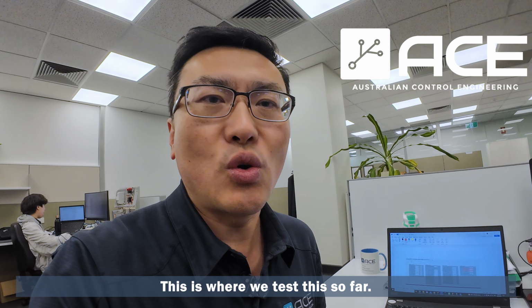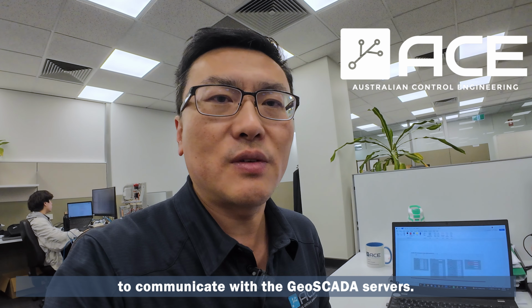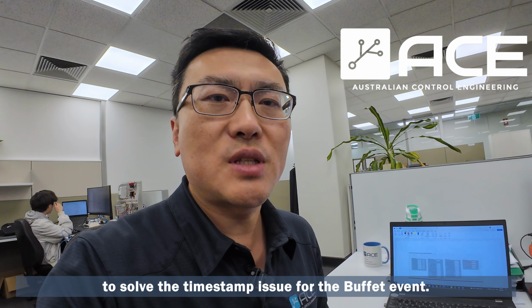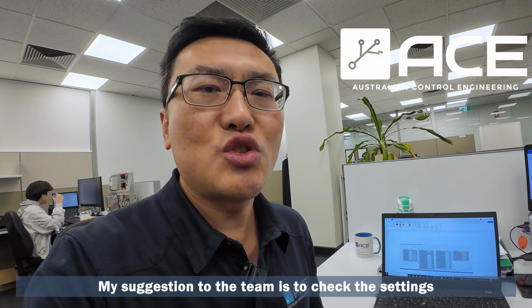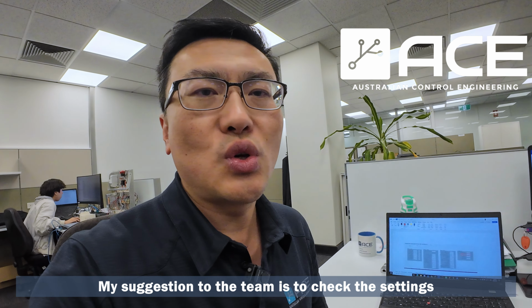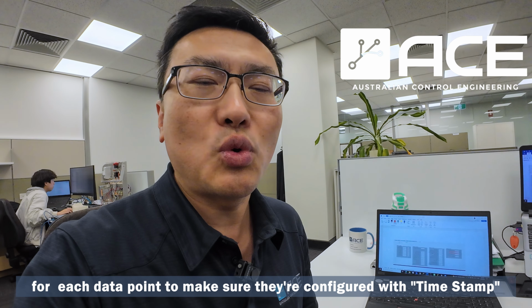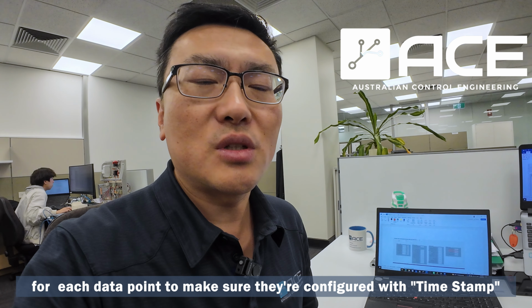This is what we've tested so far for the ProSoft DNP3 module to the GeoSCADA servers, to solve the timestamp issue for the buffered event. My suggestion to the team is to check the settings for each data point to make sure they're configured with timestamp.